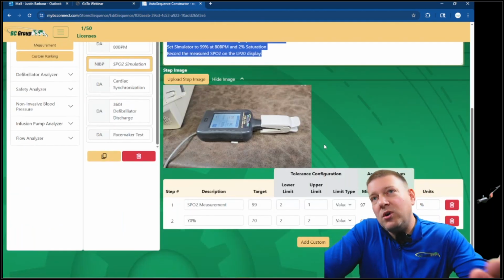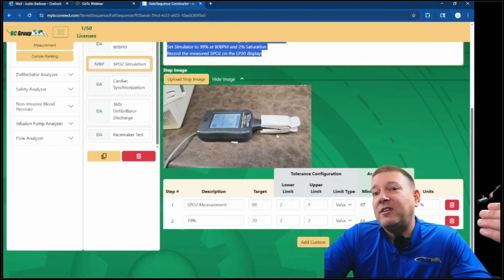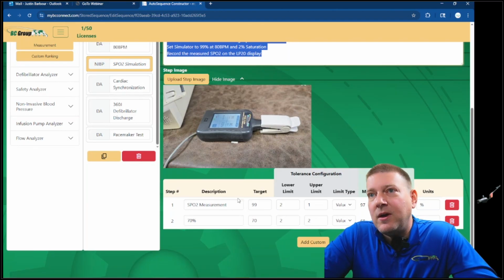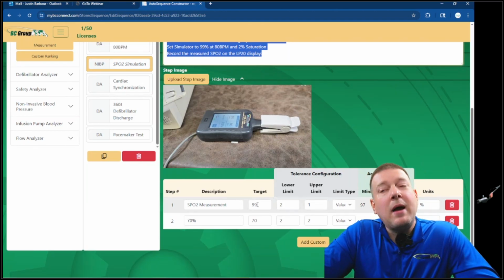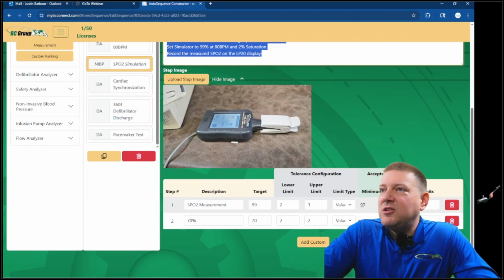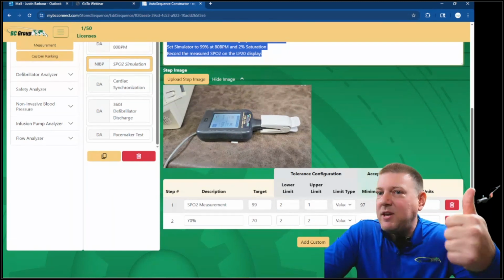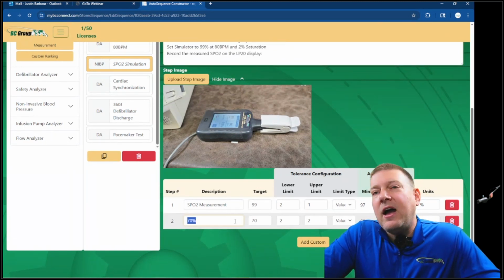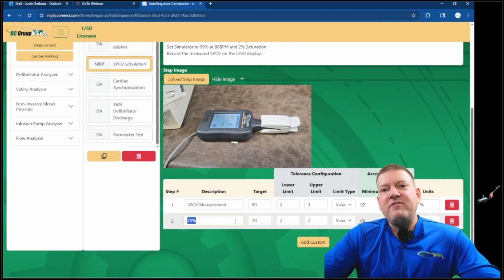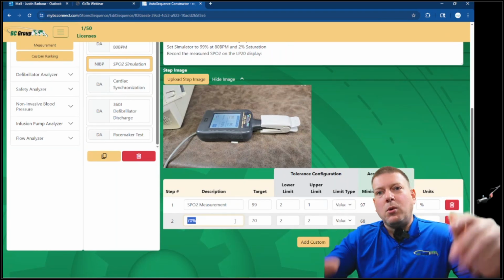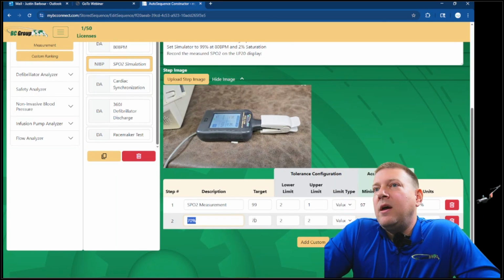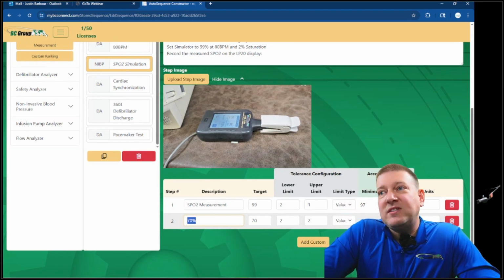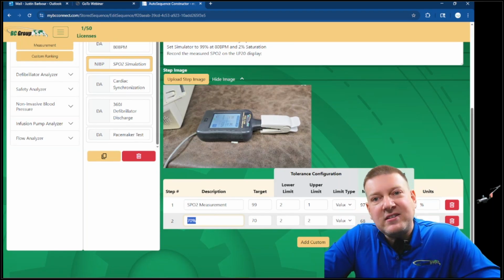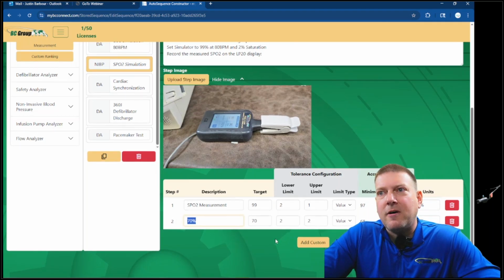And then, of course, this is another one of those things where they're going to have to type in the results they expect. So you can see my SPO2, I'm expecting 99%. As long as it's between 97 and 100, I'm happy. And then down here, I have a second test that I set up for 70%. So that gives you the upper and lower range of most SPO2. And as long as it falls between 68 and 72, again, they'll have a pass condition. Cool stuff. Very easy to set up.